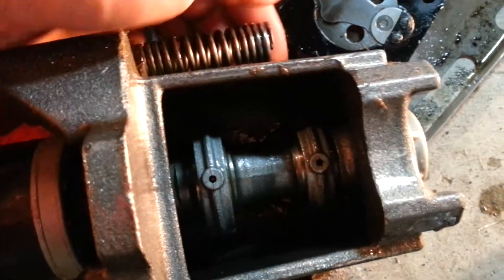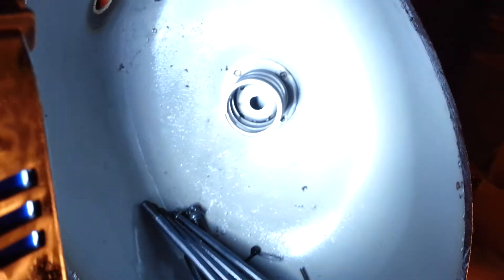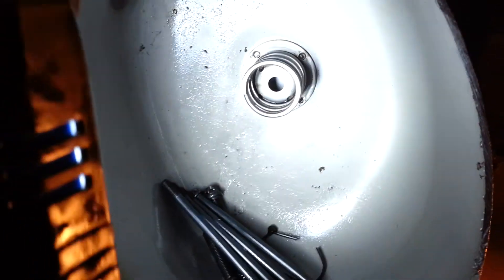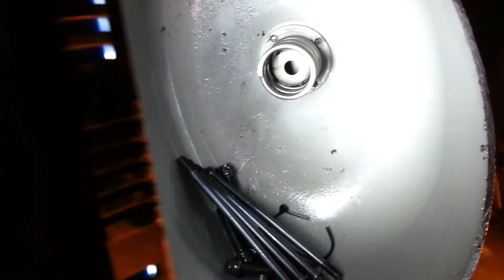The way that thing sits in there, it actually sits on these springs — here and here. You see down there, there's two pegs on either side that those springs sit on. So it's totally balanced on that spring. And then on the inside the top part sits against that spring. I'm sure you've moved compressors around and heard the clunk and clank — that's because they're all riding on springs, top and bottom. It's very cool.